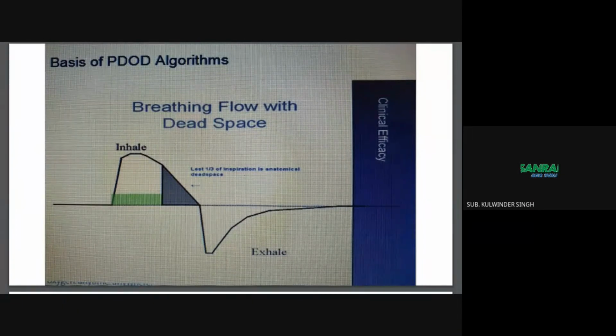So now 420 ml of the oxygen is delivered as per 20 breaths. So 420 divided by 20, that is nearly 21 ml per breath at the purity of 90. So if we calculate it, it is also the same, 19 ml of oxygen is delivered per breath by the portable oxygen concentrator, which is equal to the oxygen utilized by the patient in the stationary oxygen concentrator at the same setting. Now we are talking about the pulse mode machines.